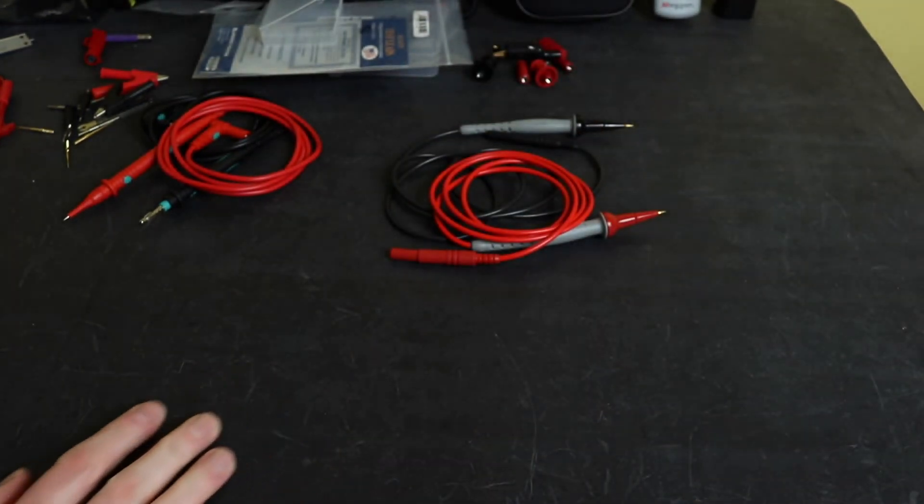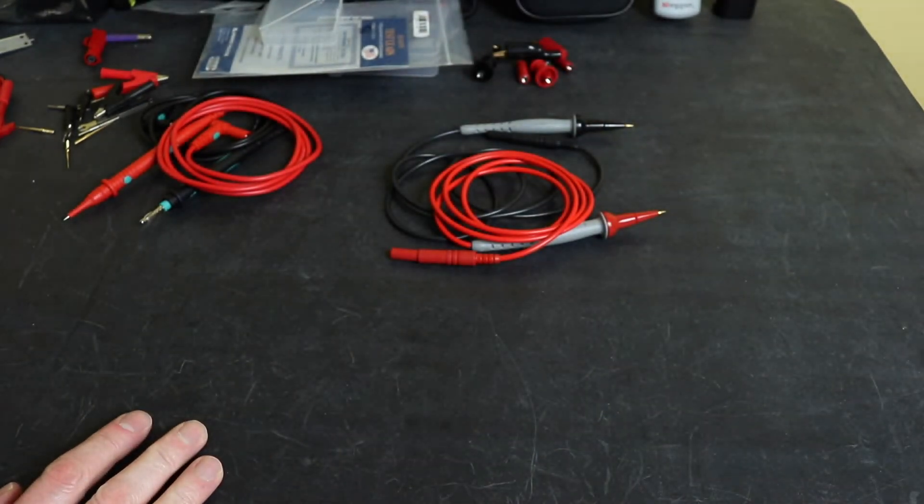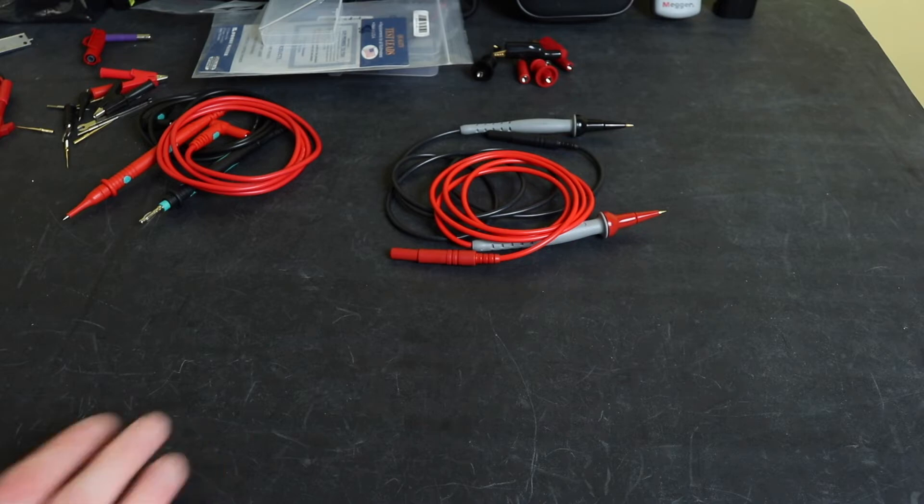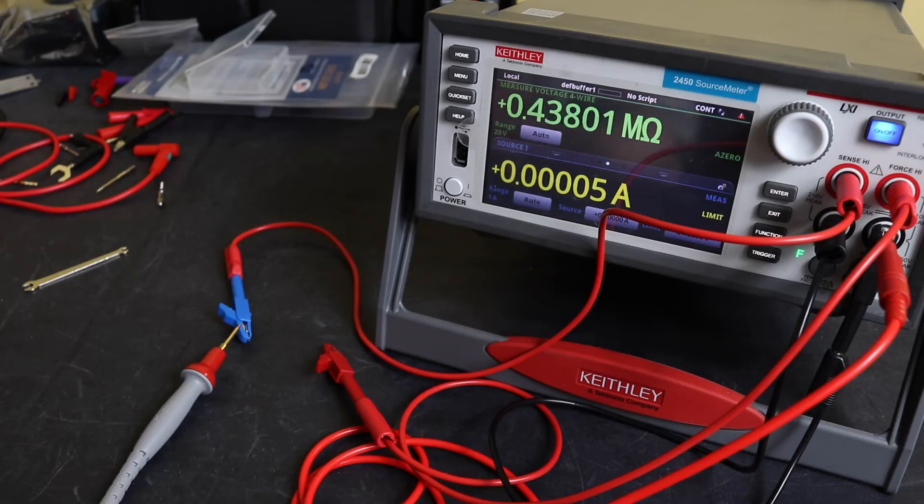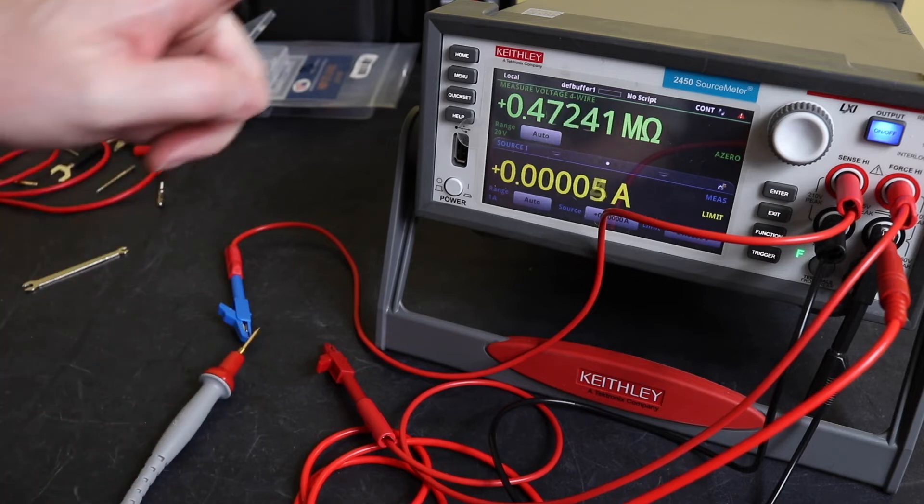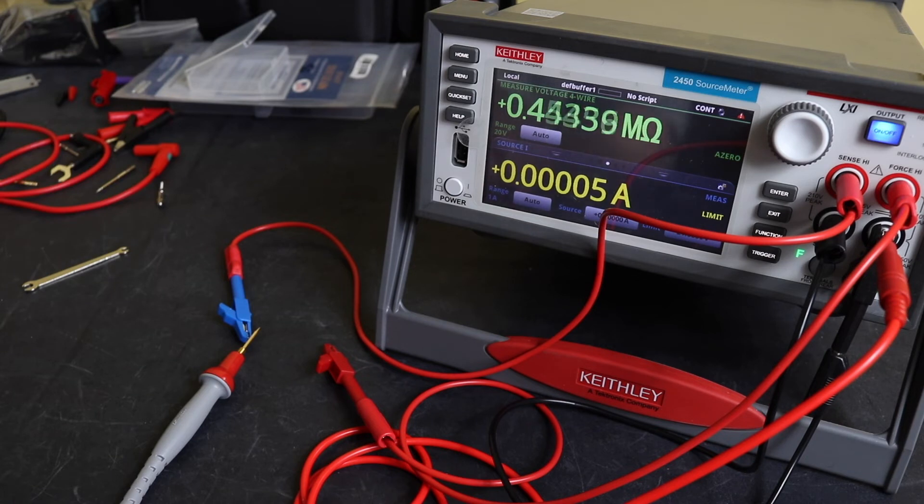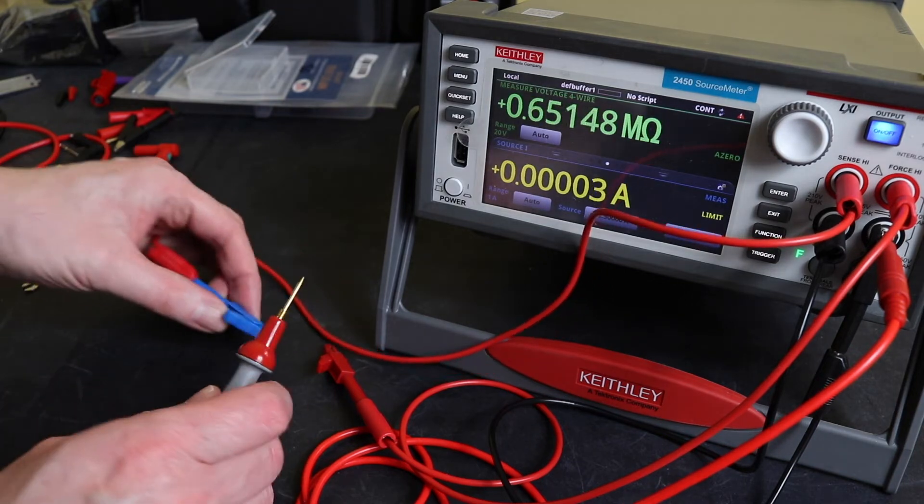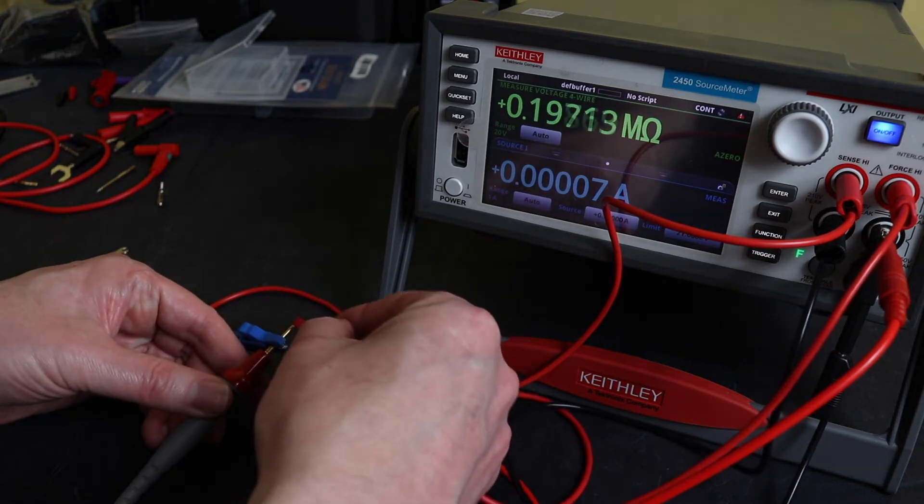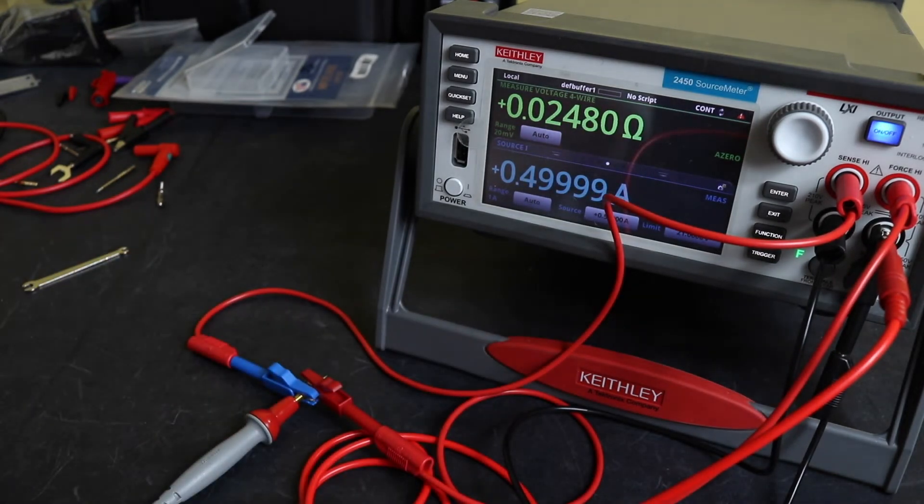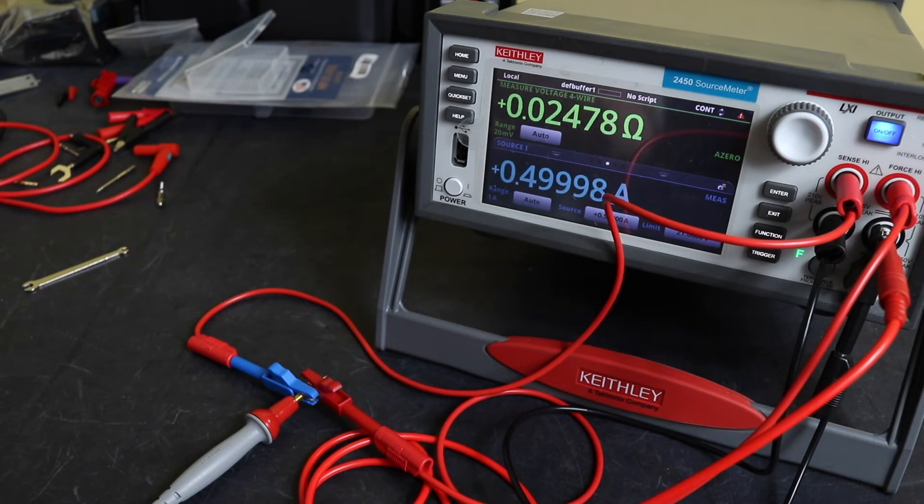I'll set up a resistance meter and make some resistance measurements on the leads to see if there's any differential between them. We're set to four wire measurement on the source meter and we're going to inject 0.5 amps, 500 milliamps, through the lead and see what resistance values we get.